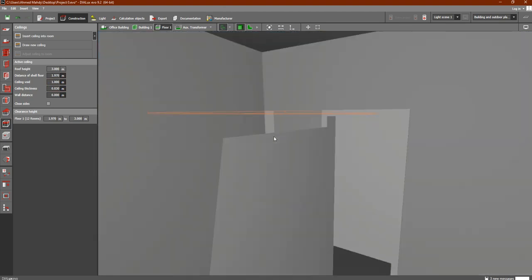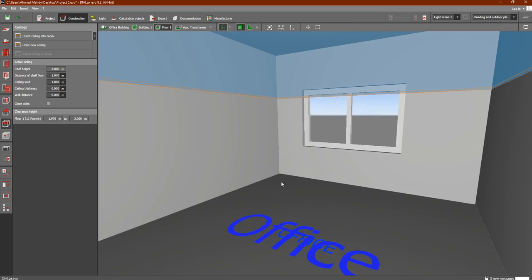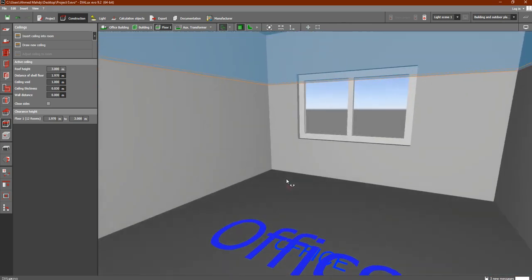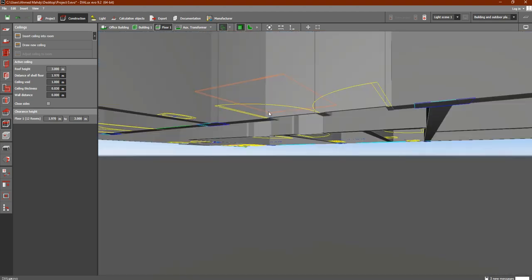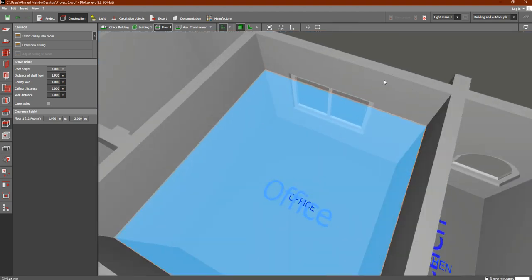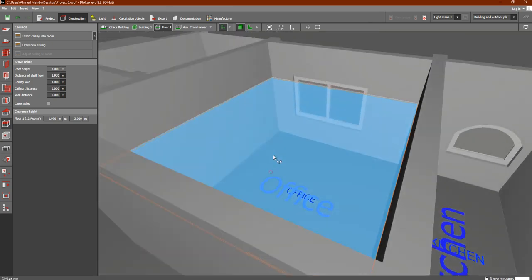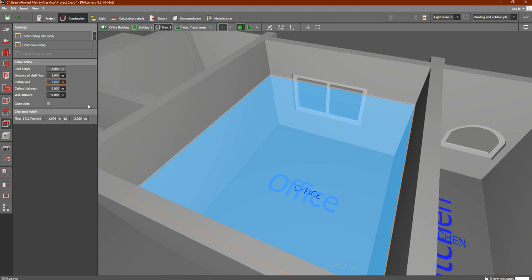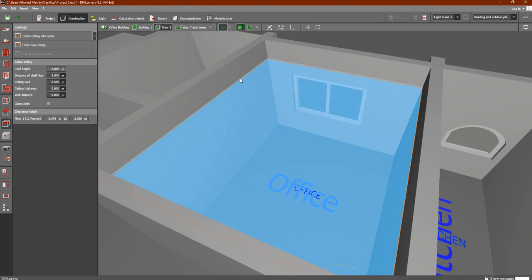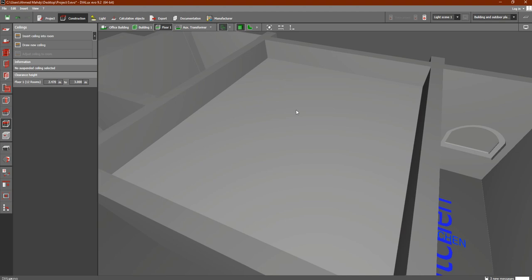We can see the extra layer of ceiling, and from this layer we attach the luminaires. The luminaires will have a distance from this new ceiling to the ground. Without this ceiling, the distance would be from the original ceiling — three meters. Now let's set it to 0.5 meters as our example. This gives us a 0.5 meter ceiling void.